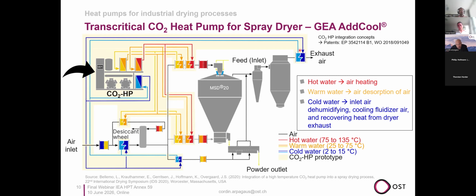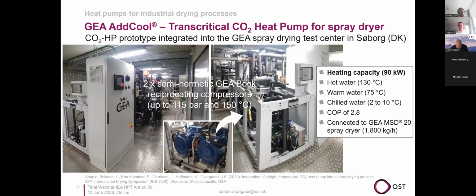Another heat source that is used is the exhaust air as a heat source for the CO2 heat pump. This has been realized in Denmark at the test center from GEA. Here we see pictures of this CO2 heat pump with 2 piston compressors from GEA Bock. The CO2 heat pump can go up to 150 degrees, let's say. It generates 130 degree hot water, and this is then used to heat up the air. The capacity of this pilot is 90 kilowatt, but it shows in principle that it works.